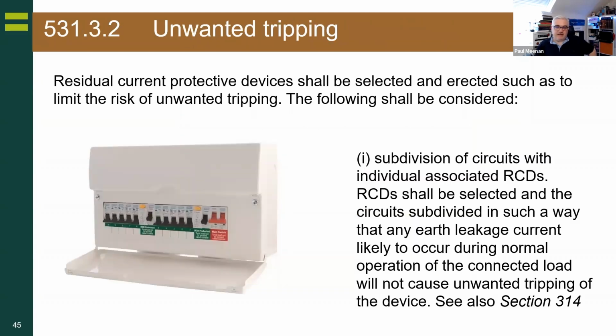So that's one of the key things. Regulation 531.3.2, back to RCDs. There is a wonderful regulation called unwanted tripping. It's quite long, but what it says is residual current devices should be selected and erected so as to limit the risk of unwanted tripping. It used to be called nuisance tripping. The following shall be considered.